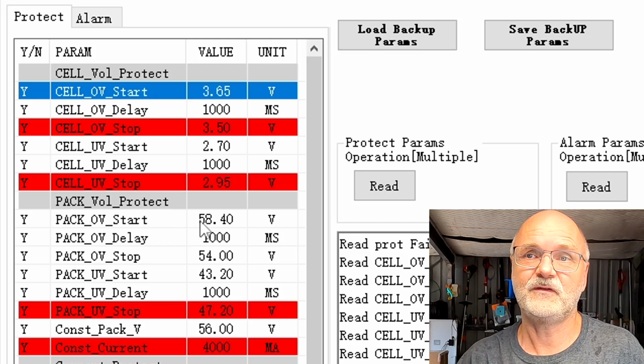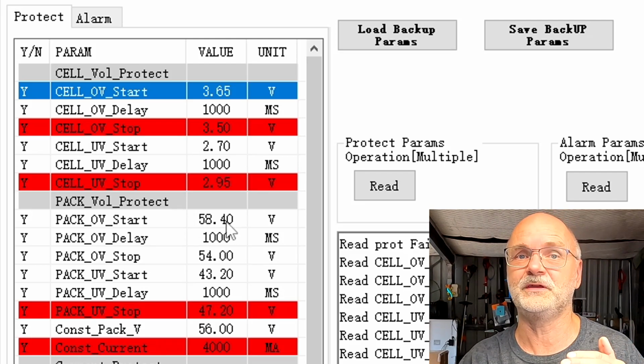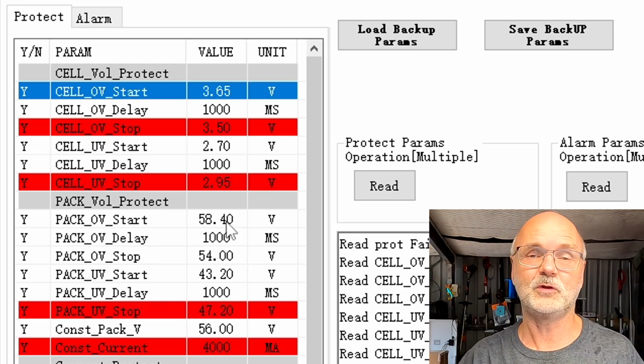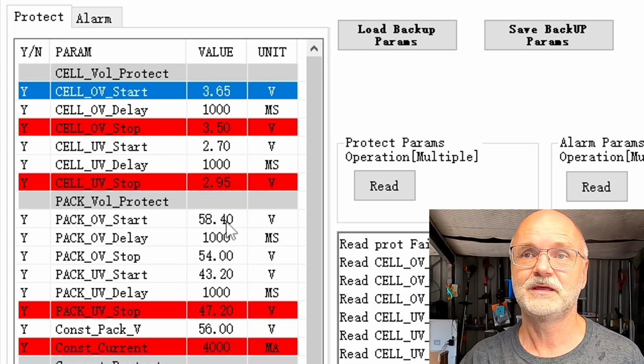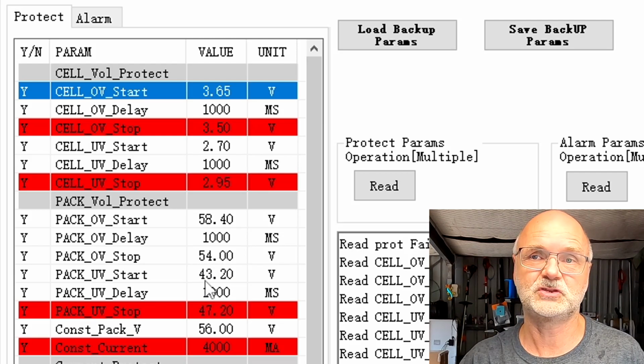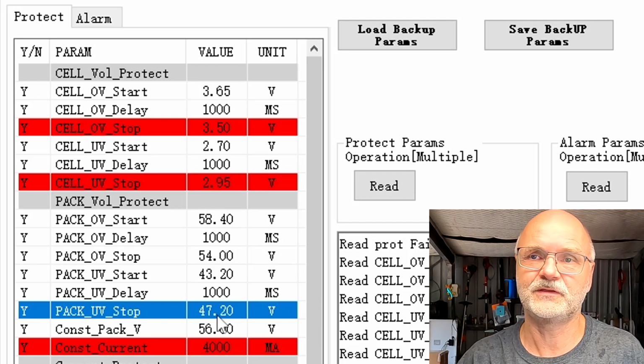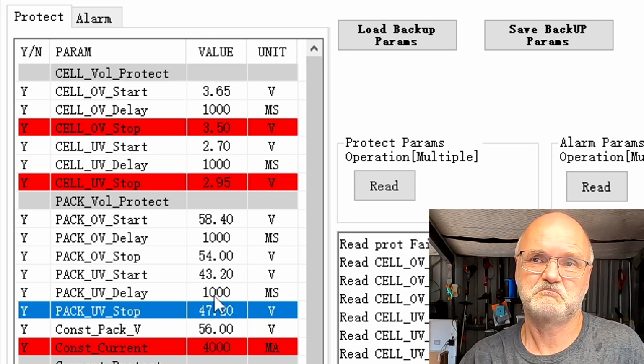For the pack, 58.4, which is 3.65 if all the 16 battery cells would be 100% calibrated, and it turns the charging back on at 54 volts. Under voltage at 43.2, and it turns on your inverter again at 47.2 volts. So no complaint, all good.